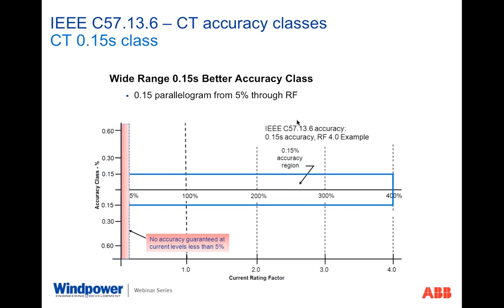That was a good move because it showed a wider range performance, but it still doesn't get us where we need to be for wind farm development. So in a way, IEEE took aim at the renewable market, but didn't quite go far enough, in my opinion. At this point, we have customers regularly speccing performance well below 5% for the reverse power measurement needs. So 0.15S is a good specification, and it meets certain needs, but if you have requirements that drop down into the pink range there below 5%, you really have to tell your suppliers your needs at that level, because if you take just the 0.15S definition, it really doesn't translate to them anything committed down below 5%. So remember that and keep in mind your best performance for the range you require.